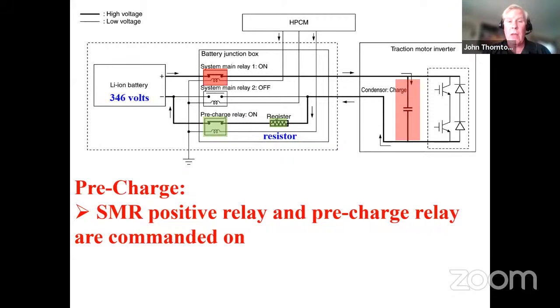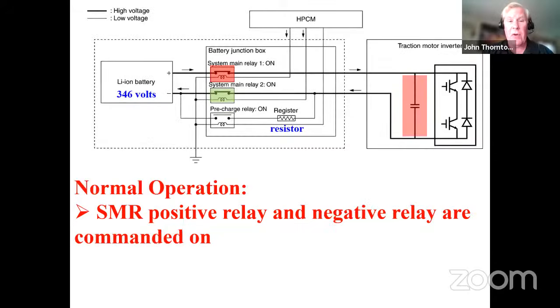But then very quickly, we're going to have to hand off. So once that capacitor is charged, and that might only take 400 or 500 milliseconds, we're going to energize main relay number 2 and de-energize the pre-charge relay. So shortly thereafter, this is what we should be left with. This is what normal operation should be. Main relay number 1 outputs the positive side of the high voltage battery, and main relay number 2 outputs the negative side. So now we have our path of current into and out of the inverter.